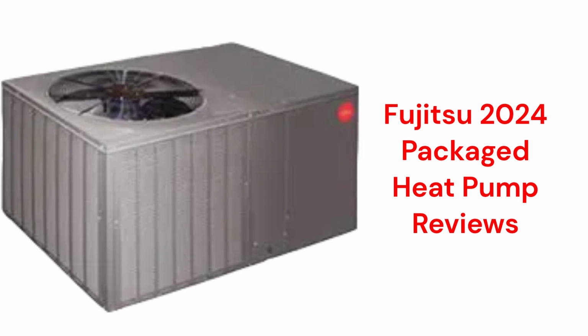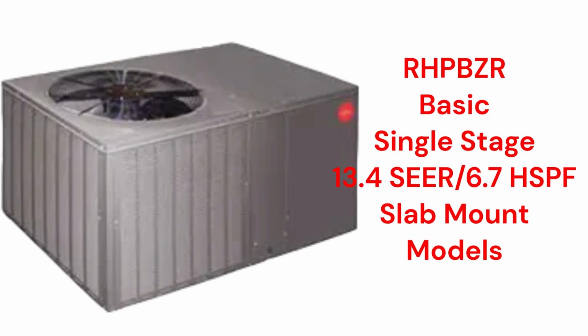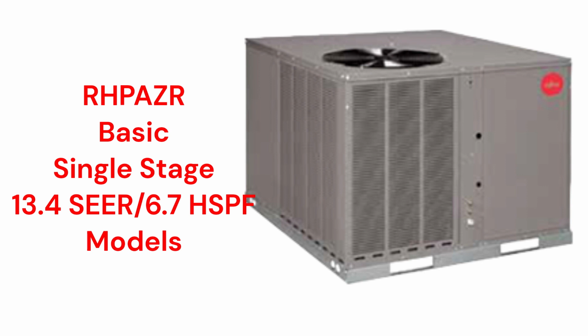They offer optional electric heat kits in sizes from 5 to 15 kilowatts to provide central heating, but they are somewhat noisy with a sound rating of 77 decibels. The RHPBZR 13.4 models are for slab mounting with horizontal air discharge, while the RHPAZR models can be installed on a roof, down discharge, or on a slab.